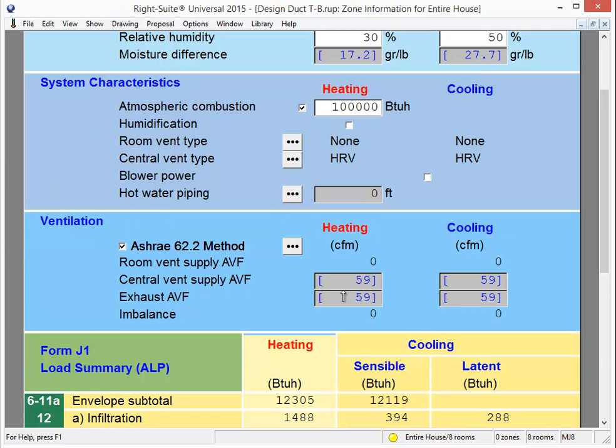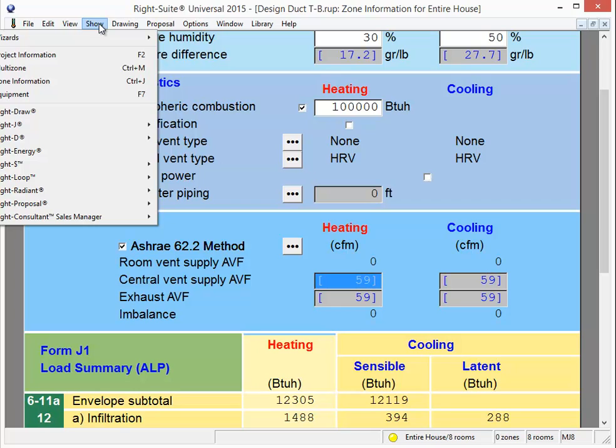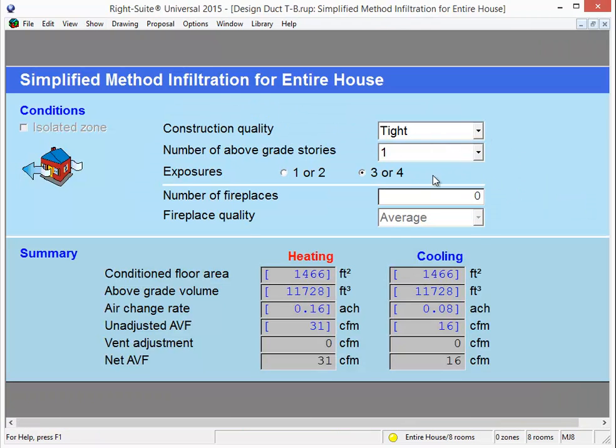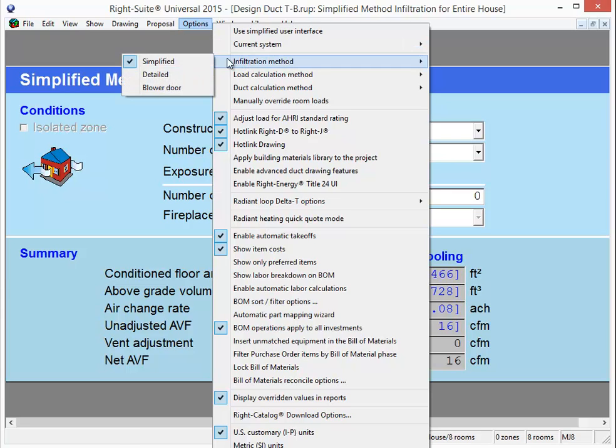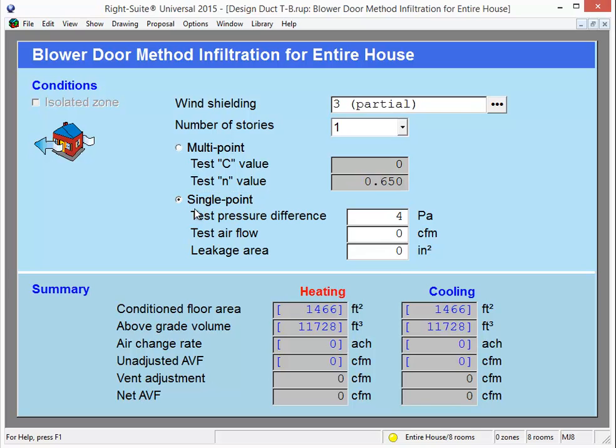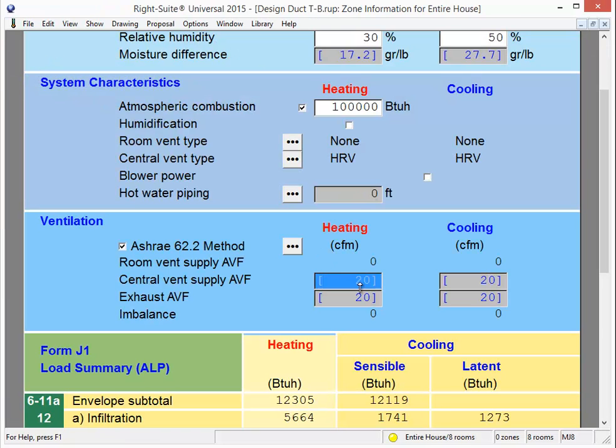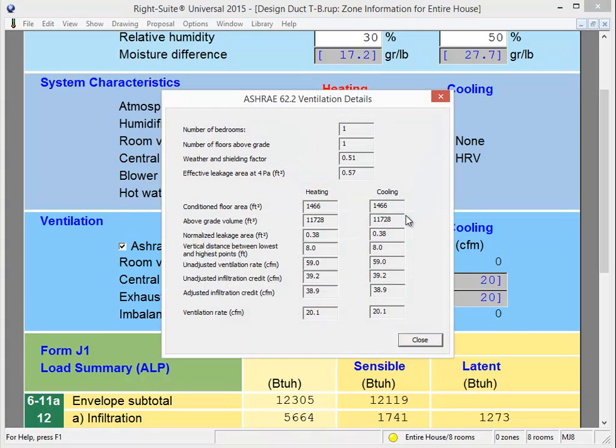Currently I have a 59 CFM requirement based on ASHRAE 62.2. If I go to my infiltration page, I'm going to show Right J infiltration. Changing the tightness of the building isn't going to do anything because you don't get an infiltration credit if you're not doing a blower door test. So I'm going to have to go to the Options menu, Infiltration Method, and switch to a blower door method. If I do, I can do a single-point test at 50 pascals, enter my CFM of leakage, and the program will calculate a natural air change rate based on that data. It will also give me credit for that infiltration in the ASHRAE 62.2 calculations. Now, instead of needing 59 CFM of outside air, I only need 20 CFM of outside air, because having switched to a blower door calculation, Right-Suite is now able to use the infiltration credits to calculate my ASHRAE 62.2 variables.